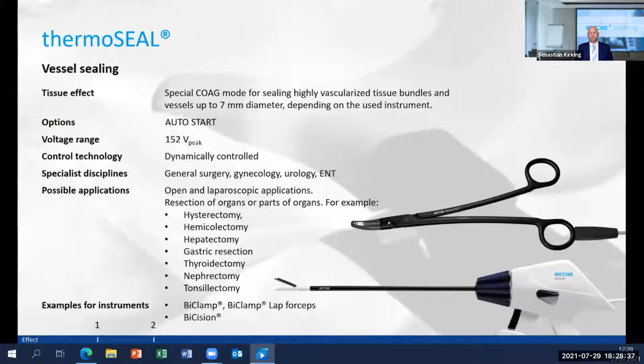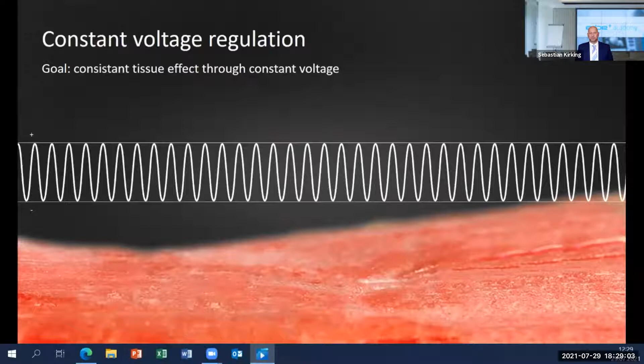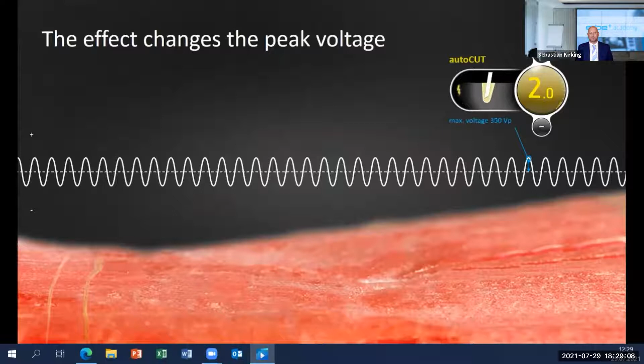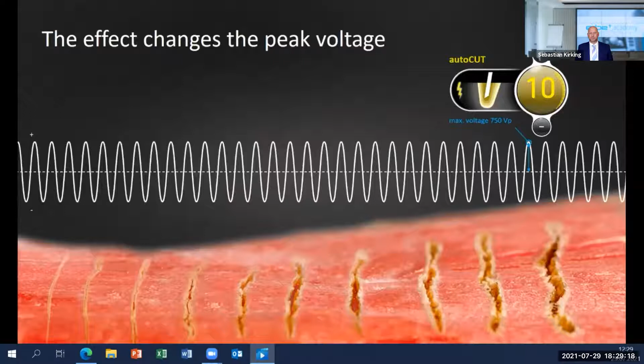Control technology is not only required for these special modes, also the regular modes must be controlled. Otherwise, the changing conditions would lead to a chaotic and uncontrolled tissue effect. Depending on the type of generator, typically either the electric power or the voltage is controlled. Ampere units have a constant voltage control. This helps to keep the tissue effect consistent. To increase or reduce the intensity of the selected mode, voltage control units let you select higher or lower voltage by adjusting the so-called effect. With high effect numbers, the peak voltage is higher, the tissue effect thereby becomes intensified.